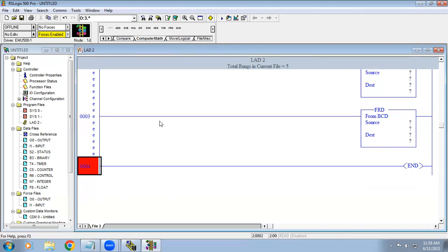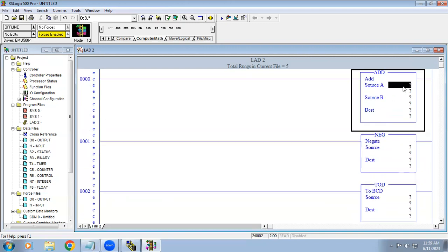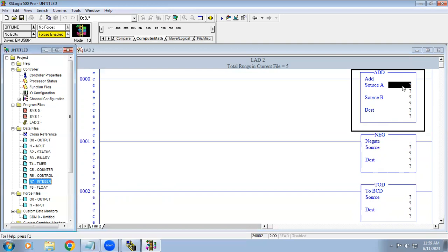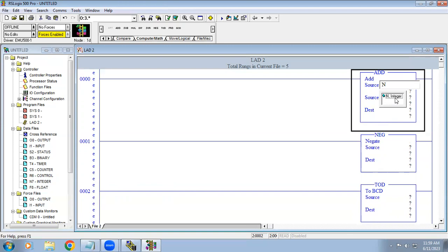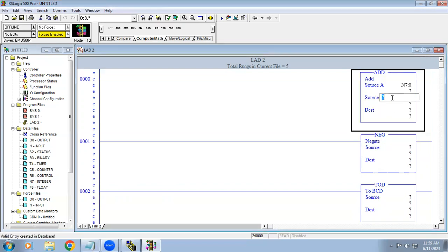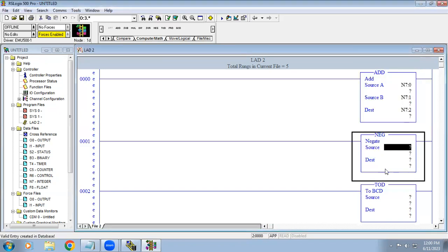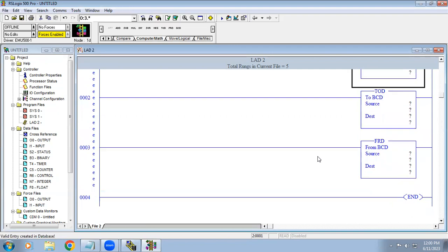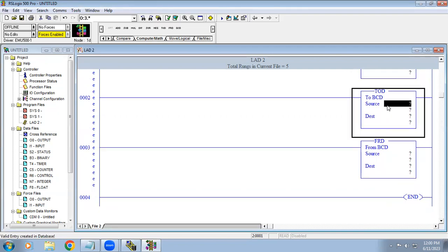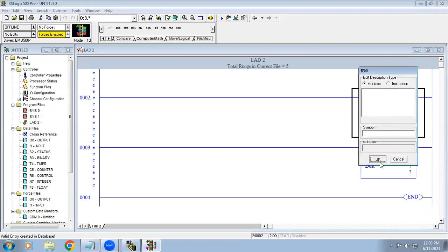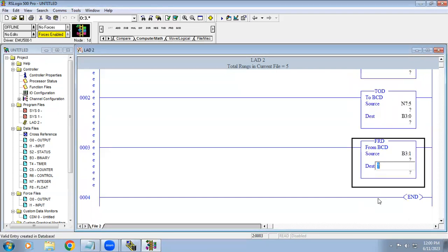For math functions we need to give a value using an integer address. In AB PLC, the integer address is N7. When you type N it will show integer automatically, and the channel number N7 colon 0 will appear. The result is stored in the destination register. For negate we use an integer address. For integer to BCD conversion we use an integer address as source and a binary address as destination. For BCD to integer it is binary as source and integer as destination.